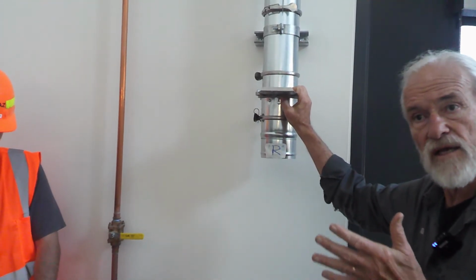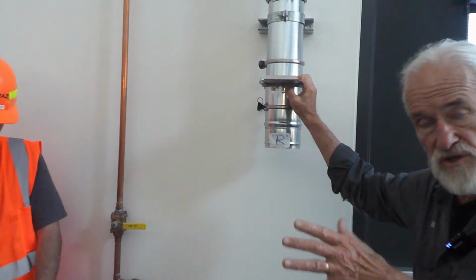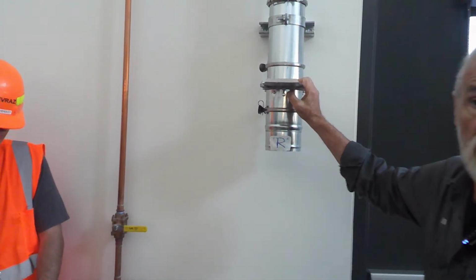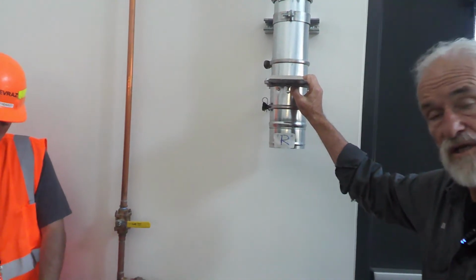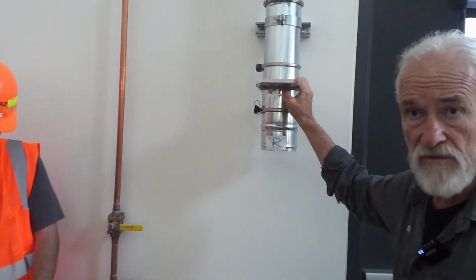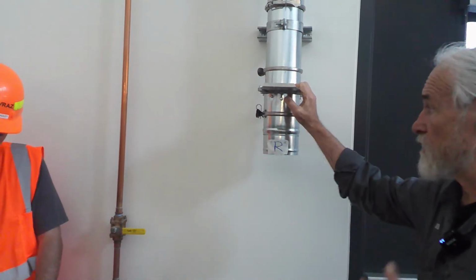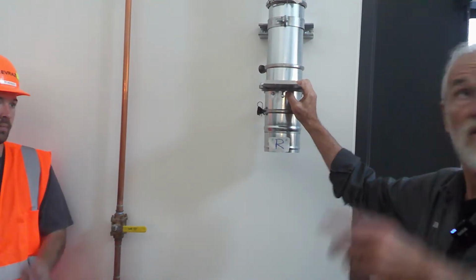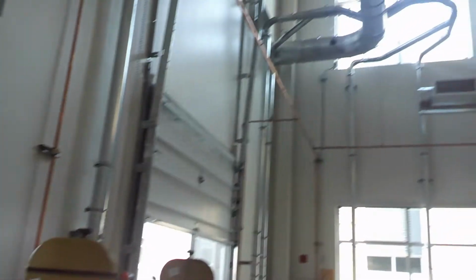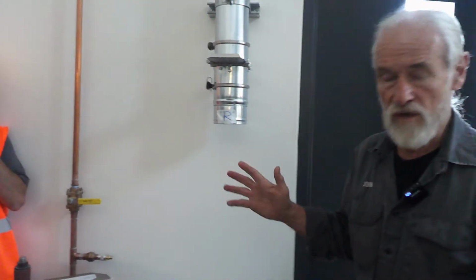Somebody should say, you can't do that, except the floor sweeps, which are open and closed. That's normal for them, the engineers take that into consideration, that's not going to be a problem. But if you cut down too much of the airflow, then the main trunk, which is this guy, allows the dust to settle in it. And if that happens, that's what burns, that's what causes problems.